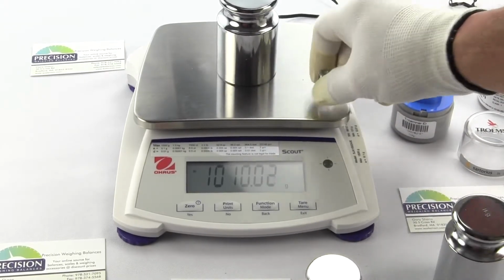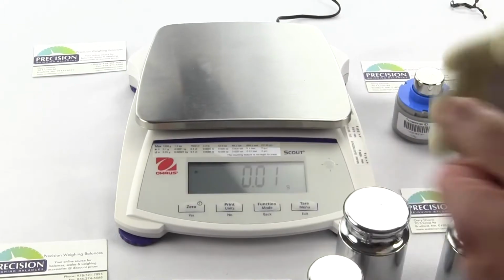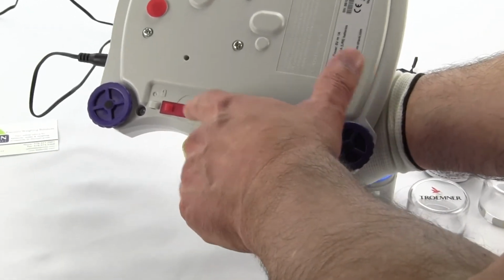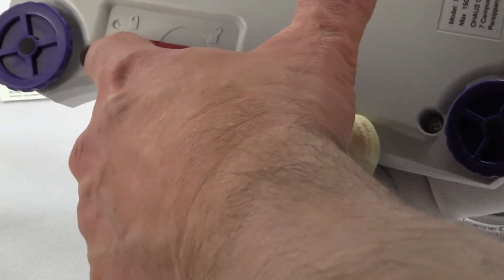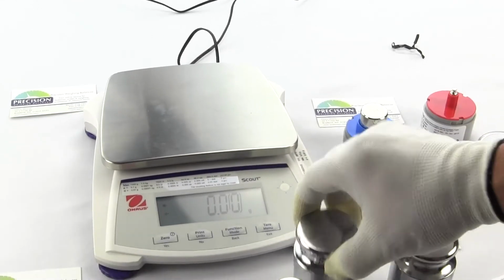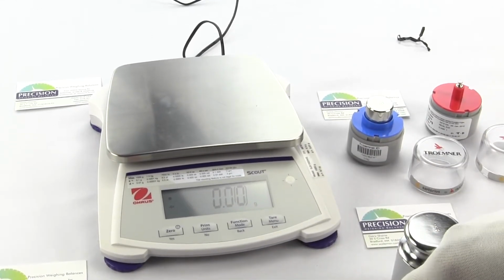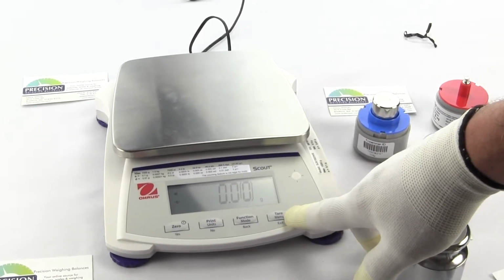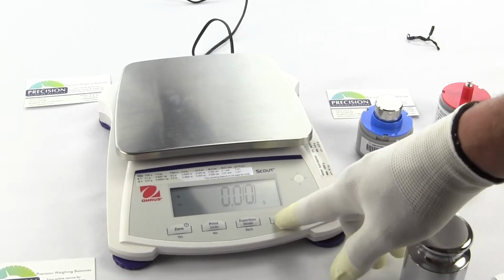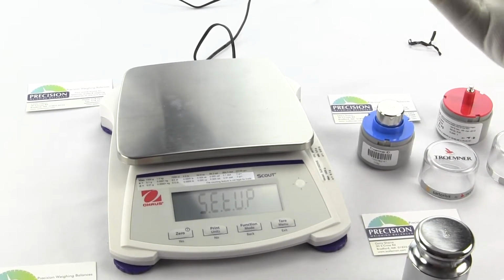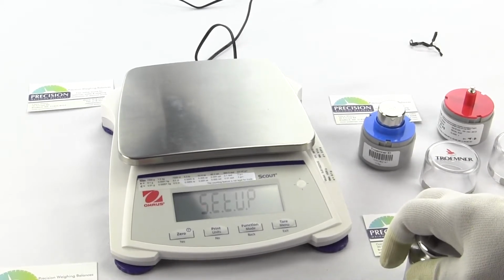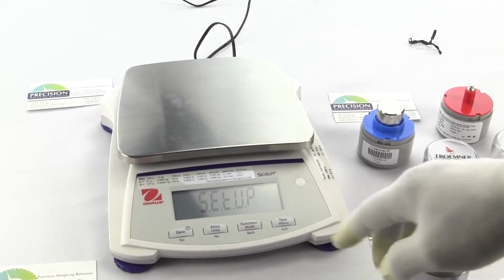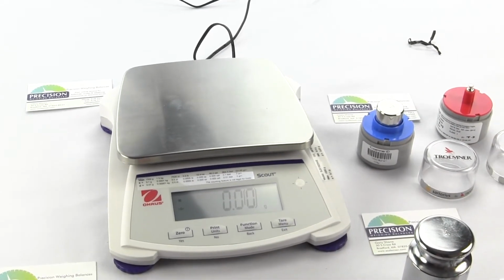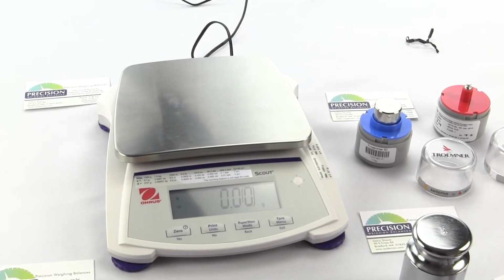Now, real quickly, we'll just pretend that I'm using this scale for a legal for trade application. Weights and Measures would lock this right here. They would either put a seal on here or they'd put a bracket. Once the scale's in legal for trade mode, you'll see the last decimal place is bracketed. If I try to calibrate the scale, I press the menu key. When menu comes up, I release and I see cal. If I do that, I release, I come to setup. There's no cal. The cal is disabled. You cannot do it in legal for trade mode. So that's the reason why legal for trade scales need to be locked out.